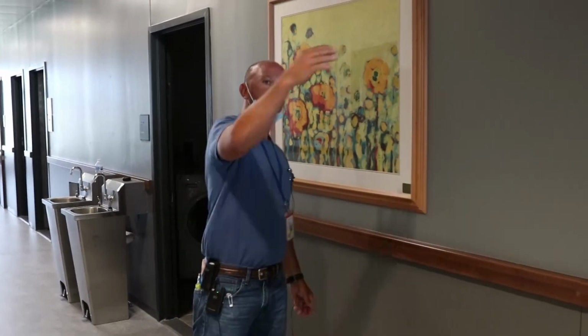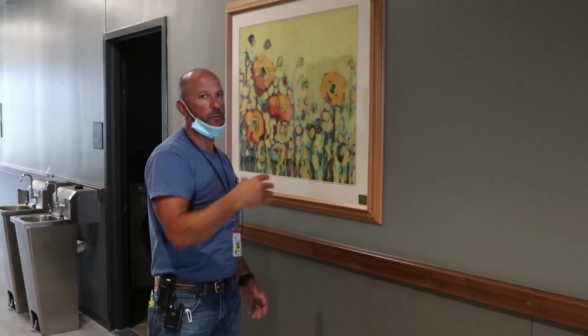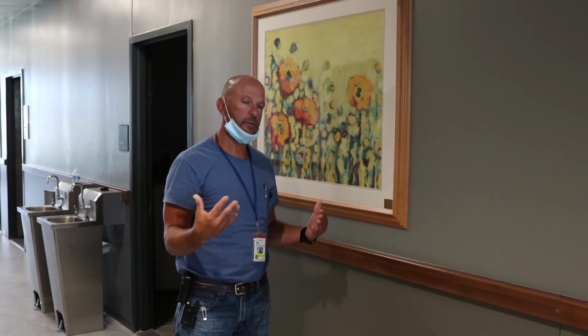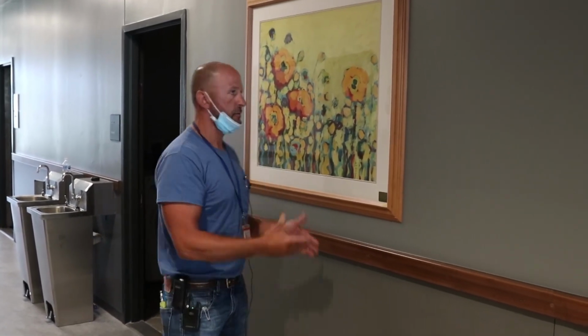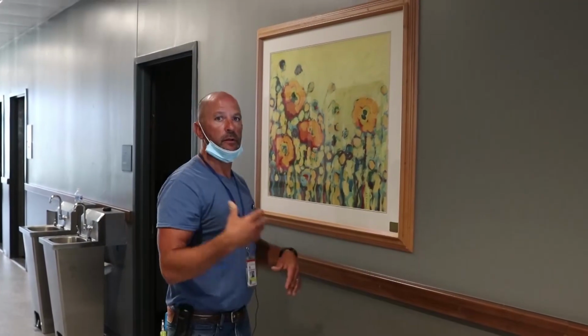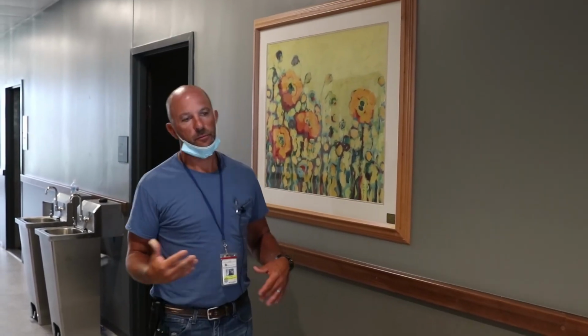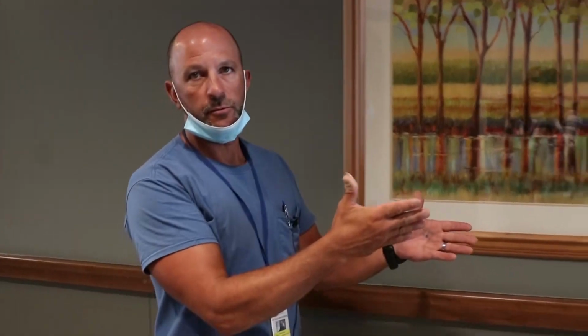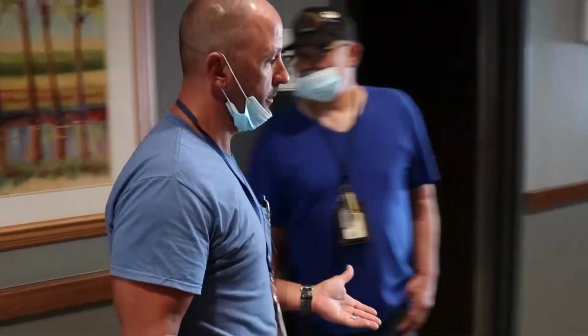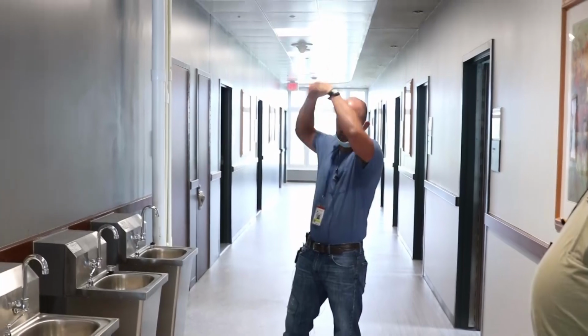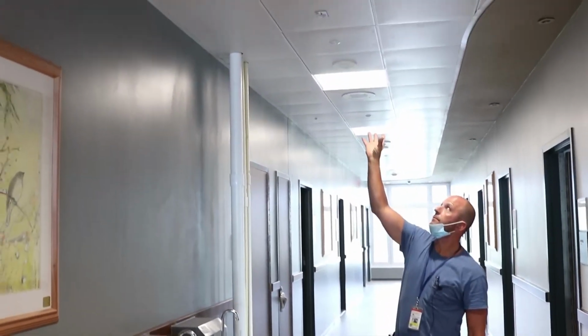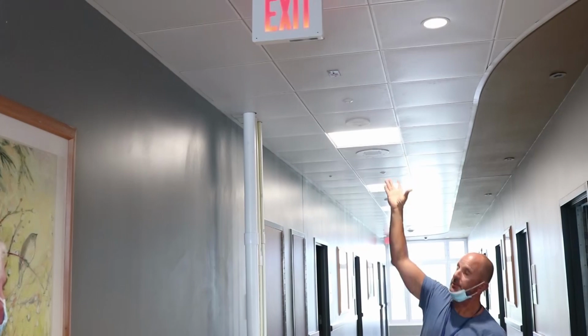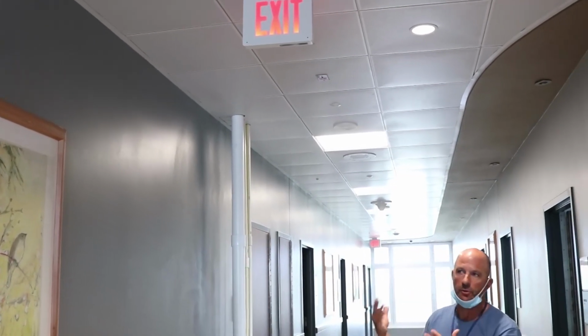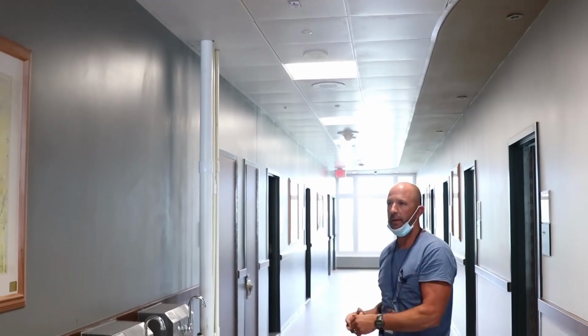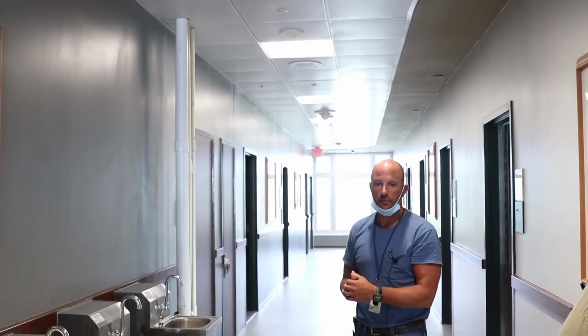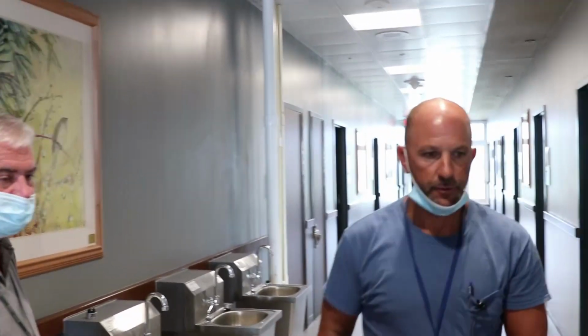If we were to continue on to the other side of this wall, which we'll just walk around, it'll be the same thing. This is floor 2, this is the bottom of this riser. So this riser sits behind us, in between 2 to 5. We'll walk around, I'll show you the other side, then we'll look at 8, and that would really be the remainder, 2 to 5. Once again, you can see what you're looking at based on the detector, but if you pop the tiles, you're going to see what you saw over there - access door, relay package, fire smoke damper access.